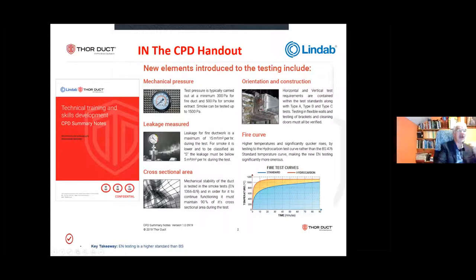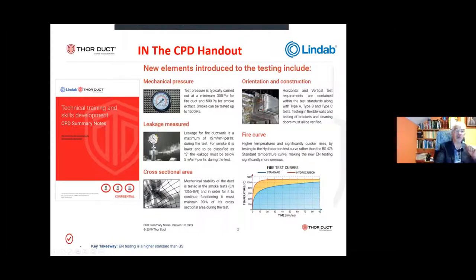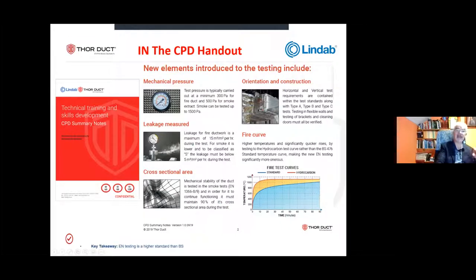The fire curve under EN is also significant. It's a hydrocarbon fire curve that reaches similar temperatures to BS 476, but gets there much faster — so the duct gets an immediate thermal shock. The 'lobster effect' under BS — where the duct had time to settle — is no longer present. The cross-sectional area and leakage requirements are the biggest changes. From a smoke control and energy perspective, that makes sense: we need the duct to perform and stay open.